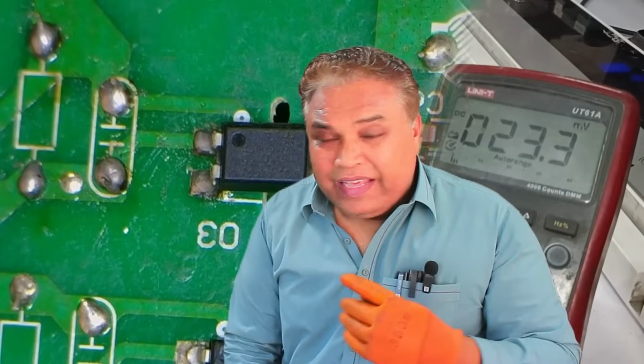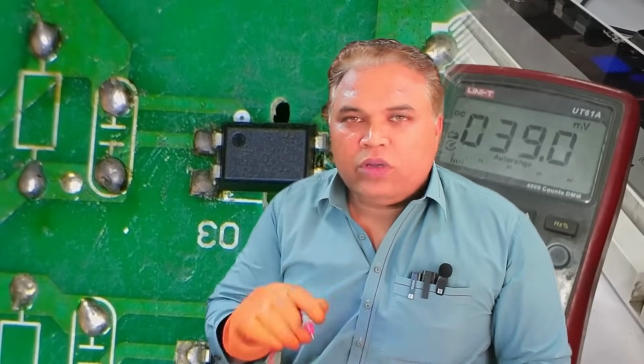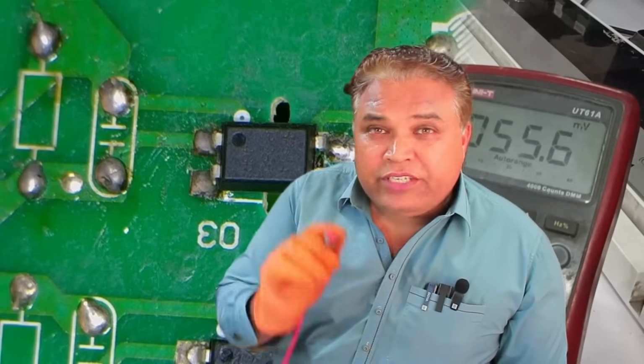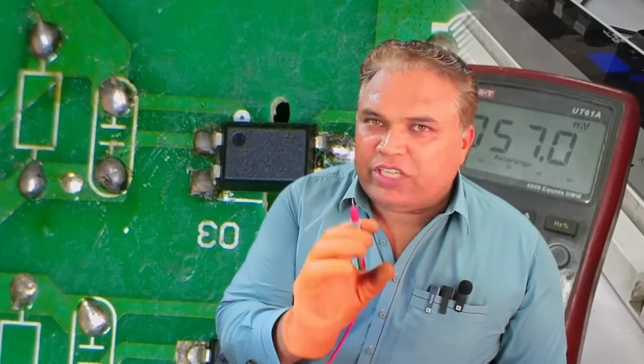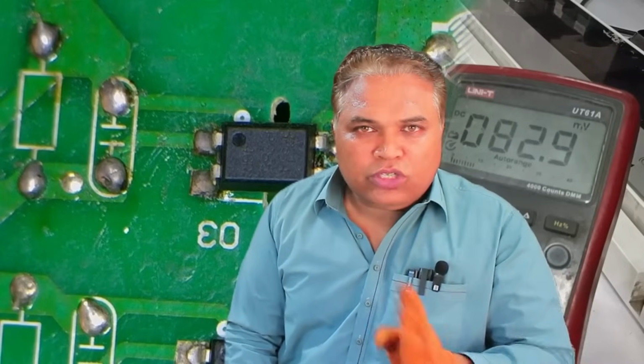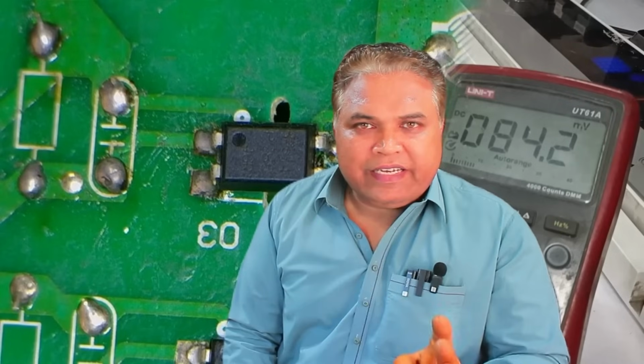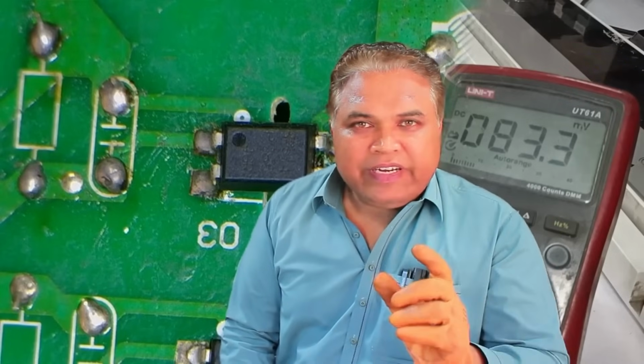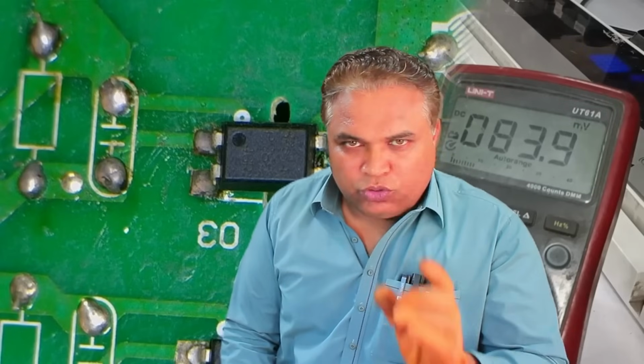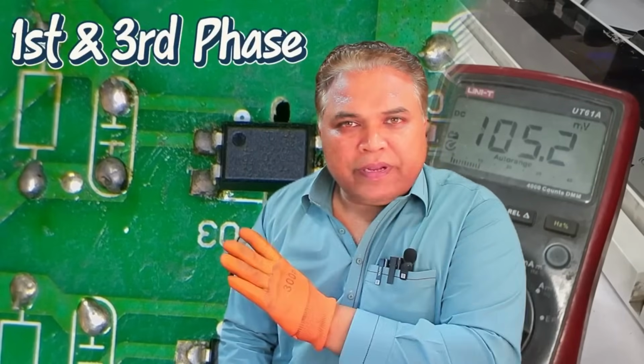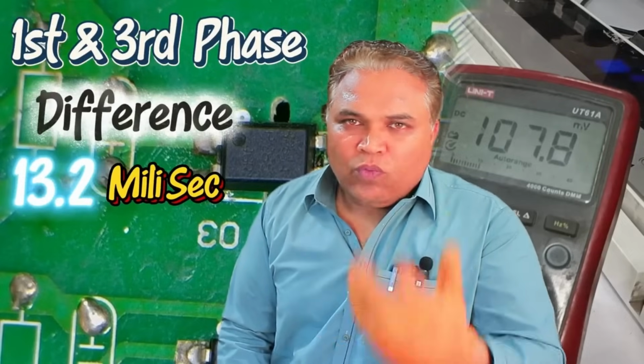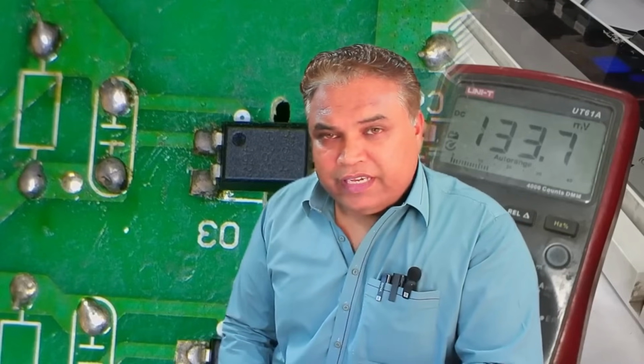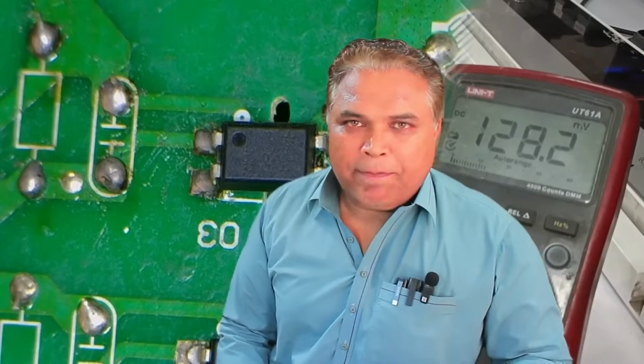However, the problem lies in the 3-phase simulation. It's not functioning properly. That's because we only generated voltage phases, but not their proper frequency and 120-degree phase difference, which is essential in true 3-phase systems. In a proper 3-phase supply, there is a 120-degree difference between each phase. This means one phase turns on and off with a 6.6 millisecond delay, and the difference between the first and third phases is 13.2 milliseconds. This time difference is essential. The setup we've made here uses just a single-phase simulated system, so it doesn't produce the correct phase shift, and because of this, the system continues to show an error.